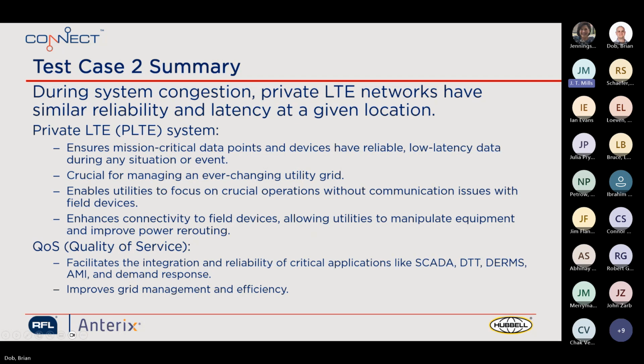But one piece also is that it allows you to have a funnel to pull as much data as you want back from those points, right? We don't always have to do SCADA points or a subset of DNP3 points. We can pull synchrophasor data back from those reclosers, those SELs. We can bring back all your DNP3 points, any of those things that the controller is able to provide. PLTE allows you to create your own size funnel to those pieces of equipment to bring as much data as you want to make operational decisions.